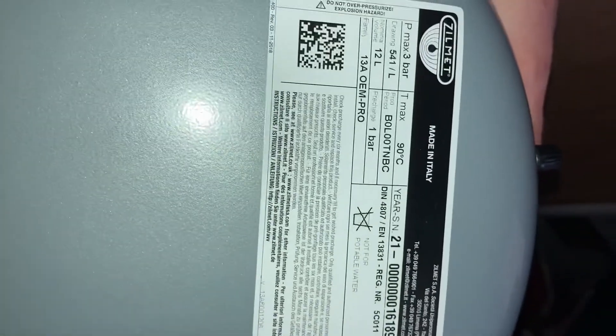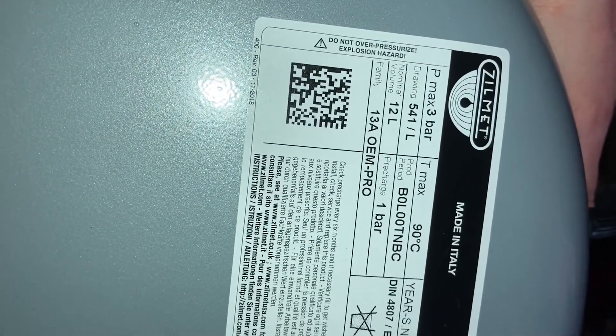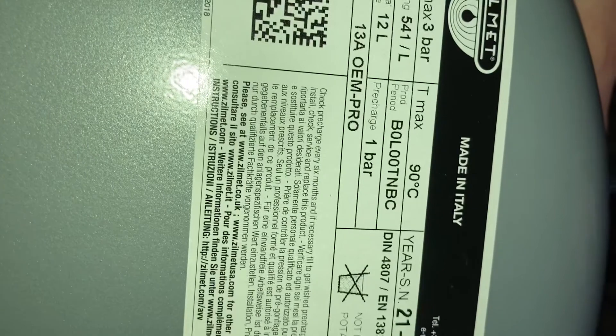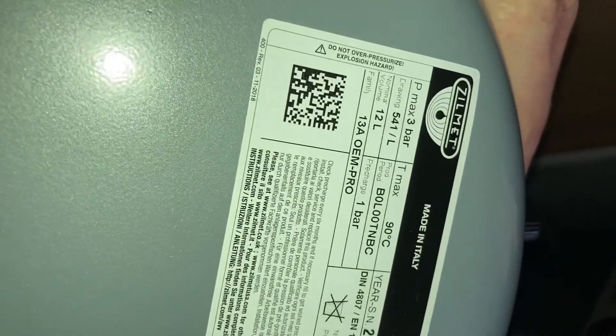Here's my replacement - exactly what is in there at the minute. It's a Zilmet 541-L and it is pre-charged to one bar. I've checked that already. It's got just over one bar in it, at about 15-16 PSI I think it was. Anyway, it's good to go. That's my replacement part I bought off eBay.